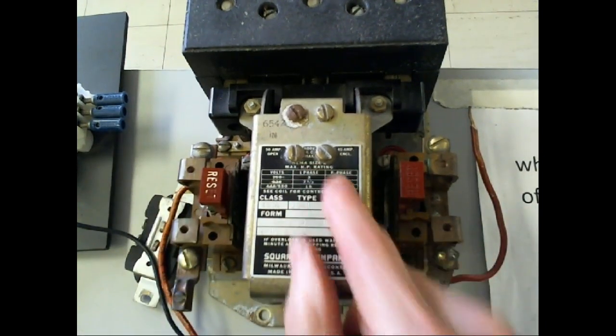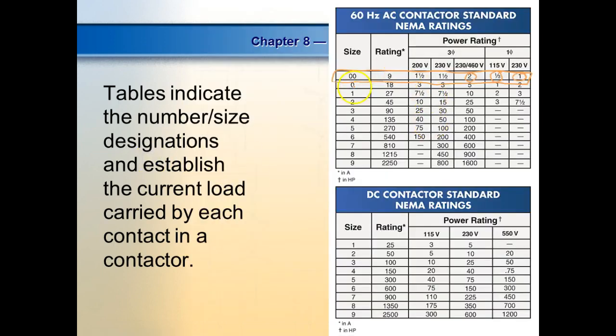So this is a size 2, three phase. So what does that mean? Well, that means this guy right here is size 2, three phase. If I was running this thing at 460, it could run a 25 horsepower motor. But it looks like at a size 9, right? It could run a what? Yeah, at 460, you could run a 1600 horsepower motor. And they had some sure enough horsepower motors up there.